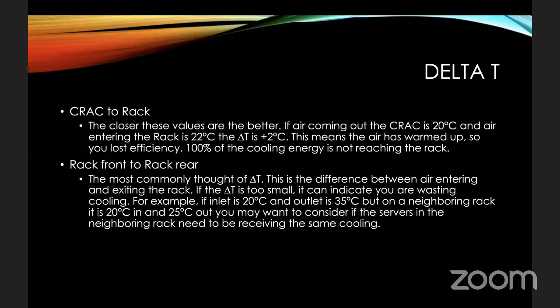The rack front to rear, which is the most commonly thought of delta T, is usually a rising temperature across the rack. A small delta T can also be an indication that you're overcooling. So for example, if you have 20-degree air coming into the rack and you've got 20-degree air coming out of the rack, the delta T is 0. Obviously, that means that you are cooling nothing. There's no temperature increase across the rack. So why are you even bothering to send cold air to that rack?